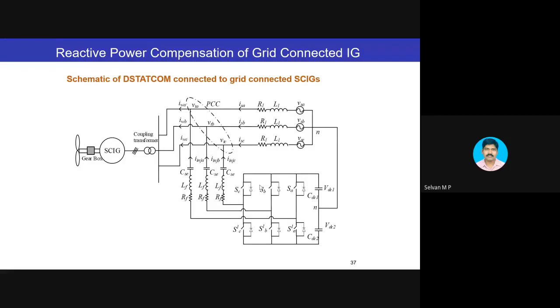But these induction machines are a load with respect to reactive power. It draws more and more reactive power. Though it is capable of supplying real power through the wind turbine, it draws reactive power to set up the magnetic flux because it is an induction machine. So if you keep on increasing more and more real wind farms with squirrel cage induction machines, there will be a problem of reactive power demand for the grid. The grid has to supply more and more reactive power for these wind farms. If the grid is not able to supply, then the voltages will go down.